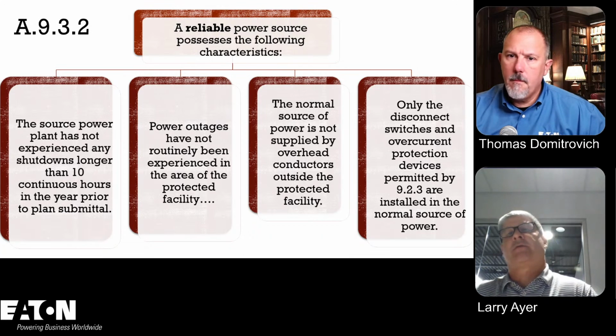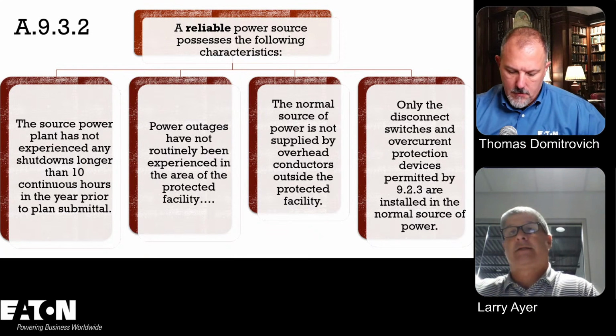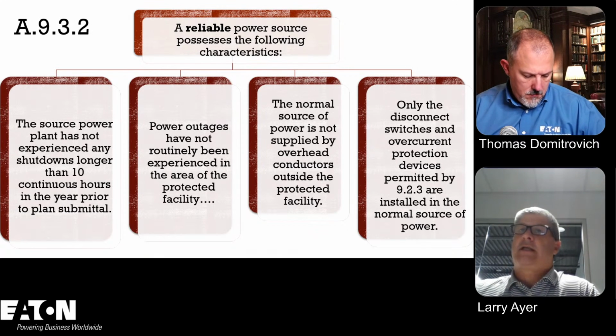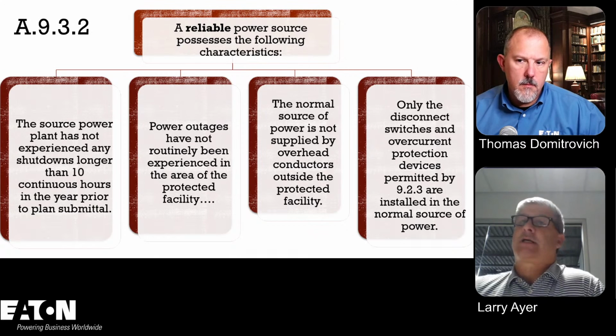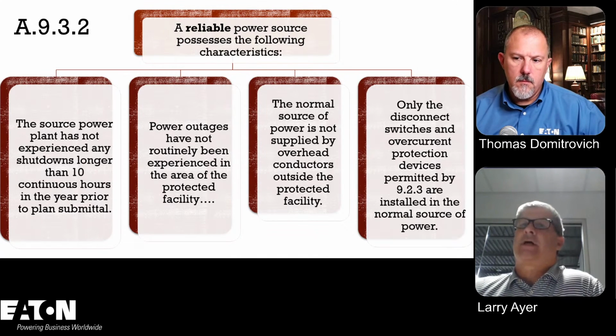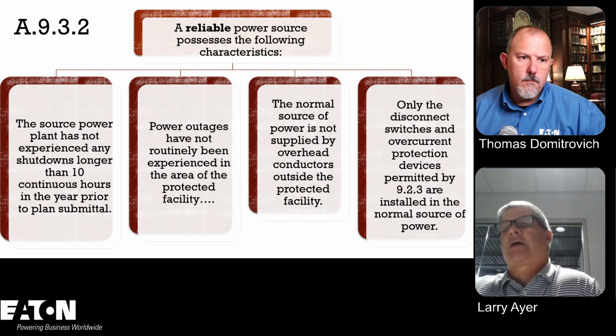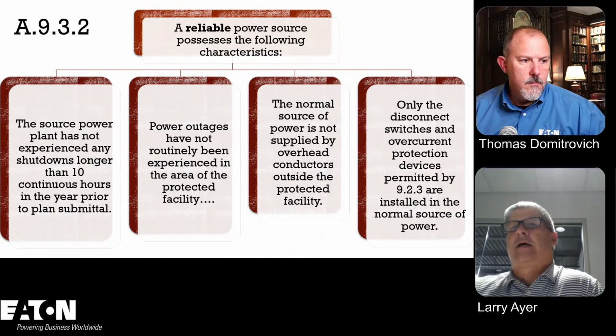If you look at NFPA 70, 695, it's really silent on what is reliable. It talks about an alternate source, but it doesn't tell you what's considered reliable. Now, if you go back to NFPA 20, we had the general requirements in 9.1. 9.2 basically says, here are the five things you can do to wire a fire pump. And then 9.3 says, but if it's not reliable, what do you do? Now, this is annex material, so this is not really enforceable, right?